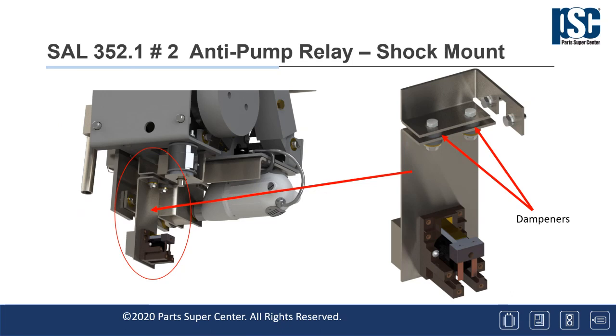Next is number 2 on SAL 352.1, which adds a shock mount for the 52Y anti-pump relay to prevent trip-free operations during closings that are caused by vibration. This change to the shock mounting became effective in 1971. The advisory is recommended to be added during the next circuit breaker overhaul. Again, ordering information will be included in the service advisory accompanying these slides. You can see on the right side the dampeners that join the 52Y support bracket to the mounting bracket above.